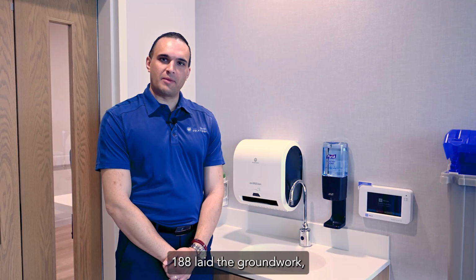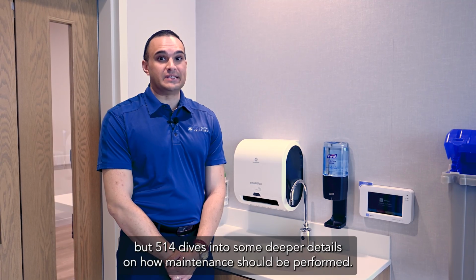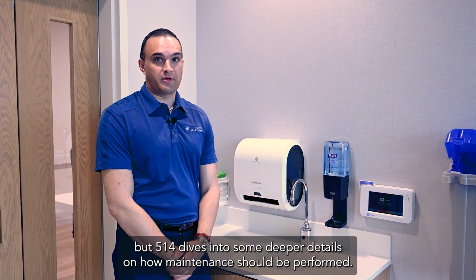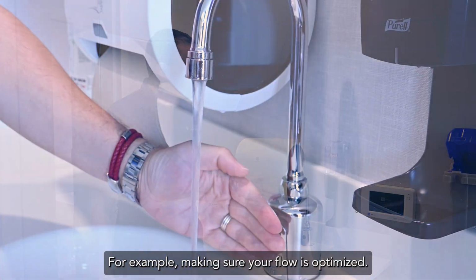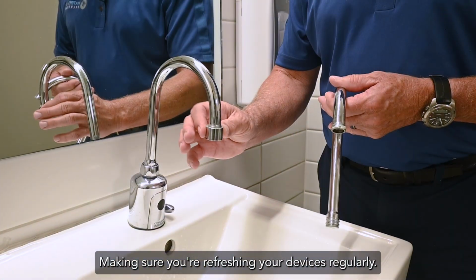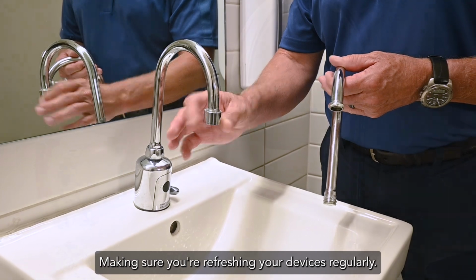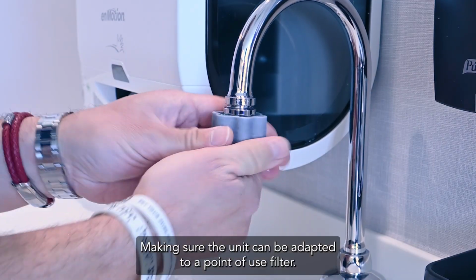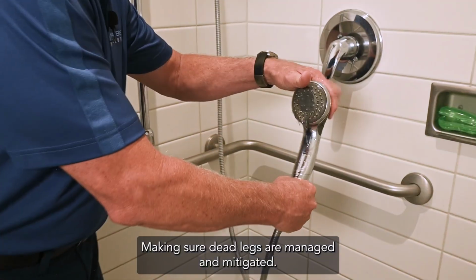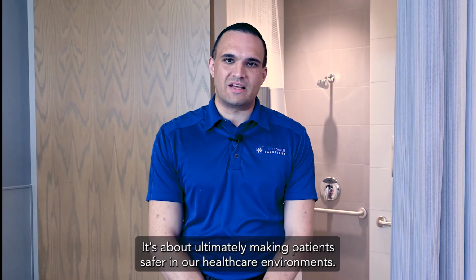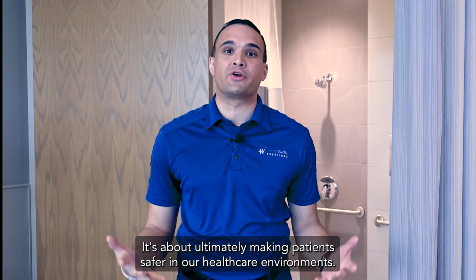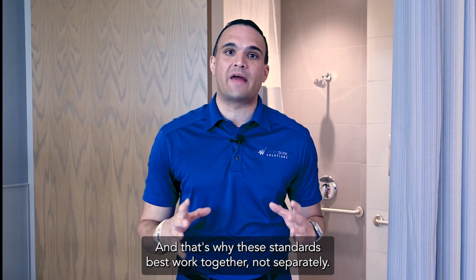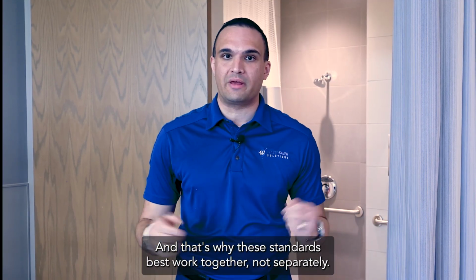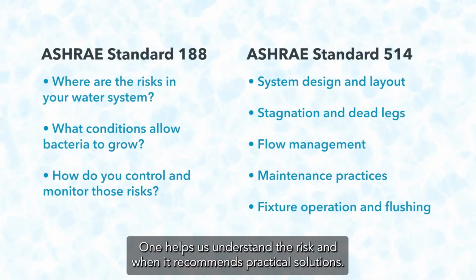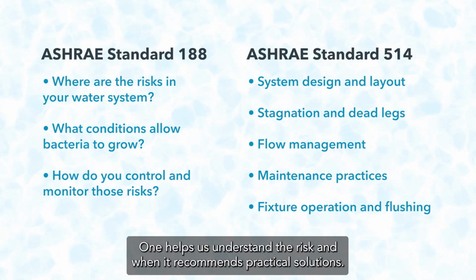188 laid the groundwork, but 514 dives into some deeper details on how maintenance should be performed. For example, making sure your flow is optimized, making sure you're refreshing your devices regularly, making sure the unit can be adapted to a point of use filter, making sure dead legs are managed and mitigated. It's not about checking boxes, it's about ultimately making patients safer in our healthcare environments. And that's why these standards best work together, not separately. One helps us understand the risk, and one recommends practical solutions.